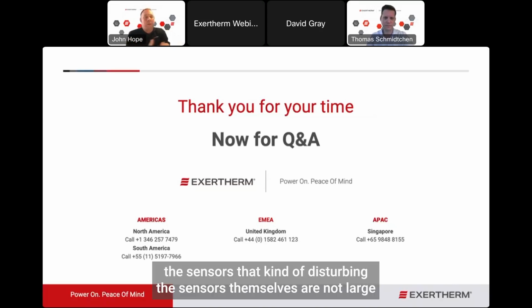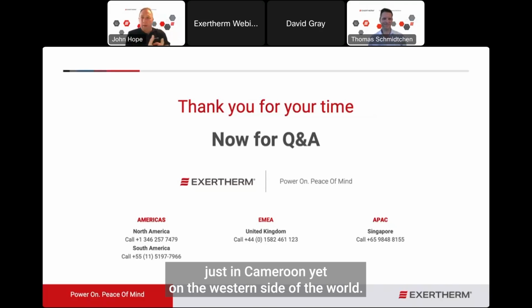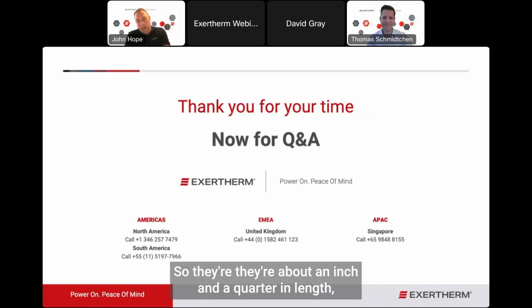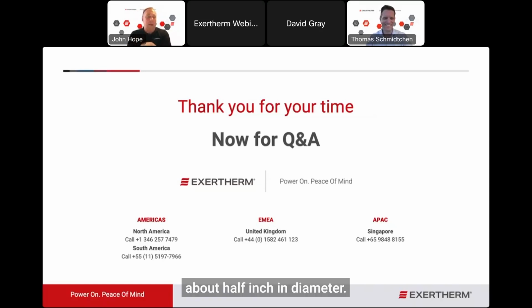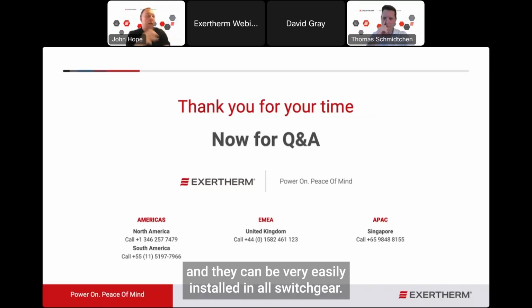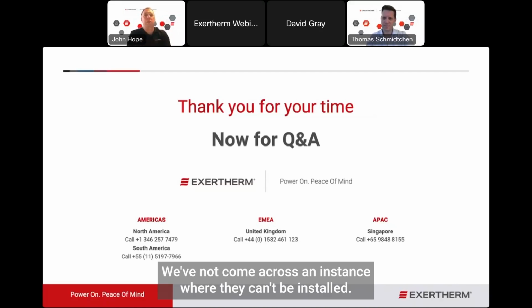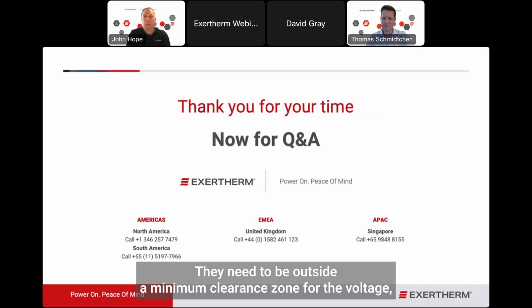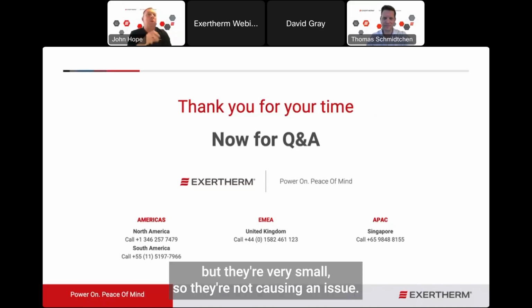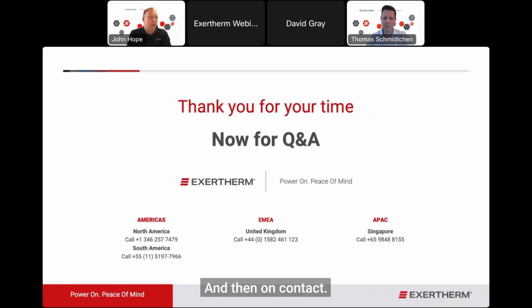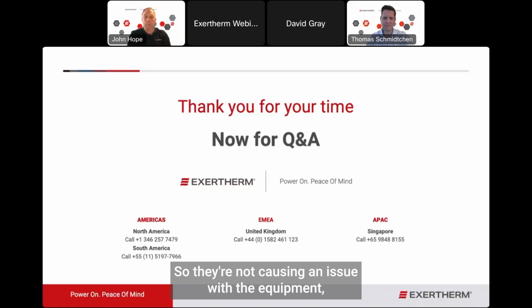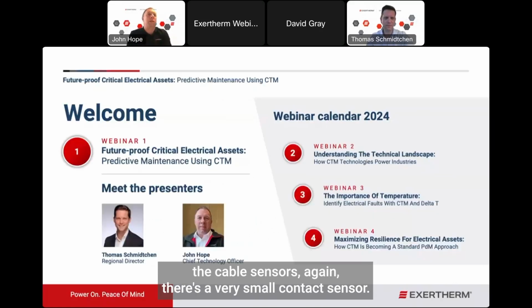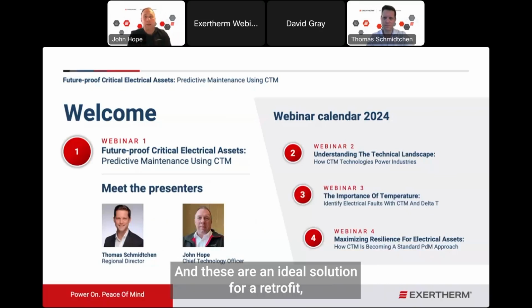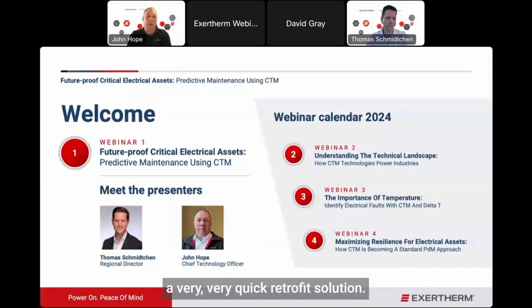Yes, the sensors themselves are not large. Thinking we're in the western side of the world, they're about 1.25 inches in length, probably about 1/2 inch in diameter. So they're very small, they're unobtrusive, and they can be very easily installed in all switchgear. We've not come across an instance where they can't be installed. They need to be outside a minimum clearance zone for the voltage, but they're very small. So they're not causing an issue. They don't cause a type test issue. And they're non-contact. So they're not causing an issue with the equipment. The cable sensor, again, is a very small contact sensor. It simply cable ties on and is an ideal solution for a retrofit. A very, very quick retrofit solution.